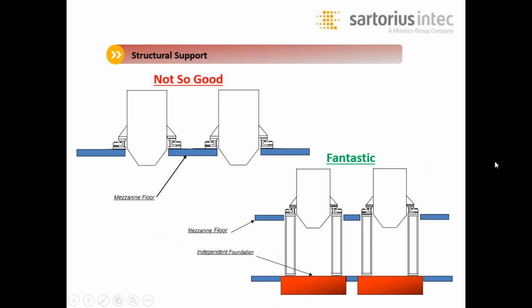Okay, tanks that are installed directly on mezzanine structures are subject to problems such as cross interaction. As the tank next to it fills and empties, mezzanine floors flex. It can also be caused by people walking next to the vessel, vibration from nearby equipment, and many other factors. Another example of tank-to-tank interaction is shown on the top left here. A properly designed system would include an independent foundation and structural support for the weighing assemblies. If you have an application where high resolution is important to the customer, then adding these extra structural members will definitely improve their resolution and the output of the weighing system.